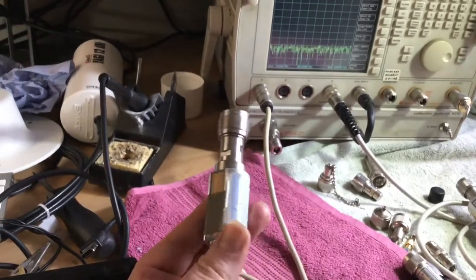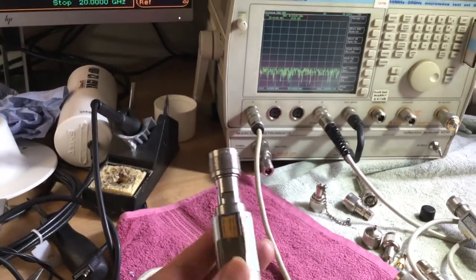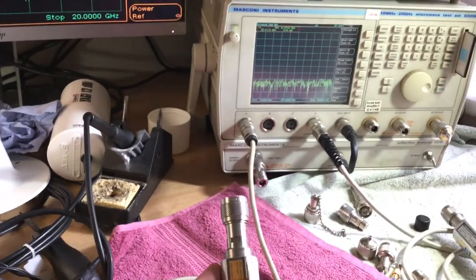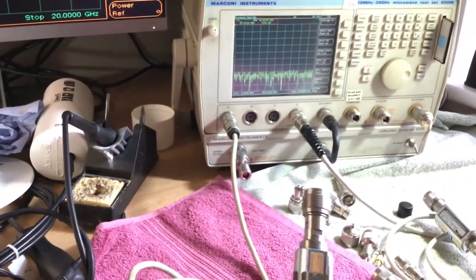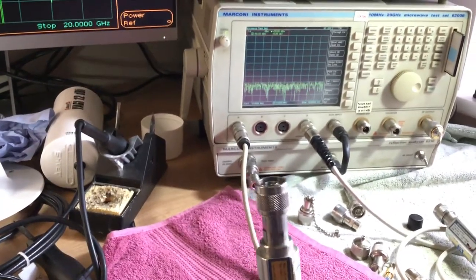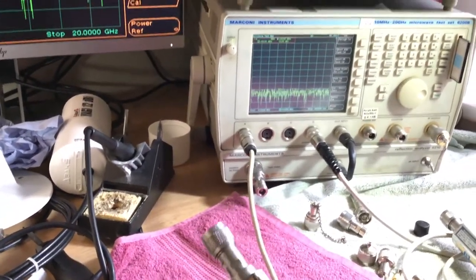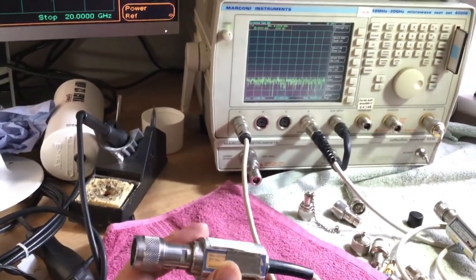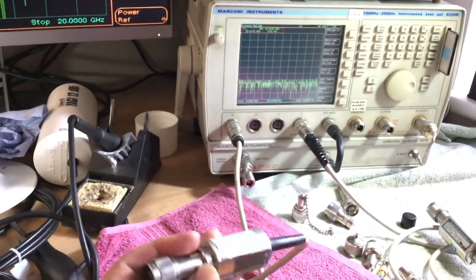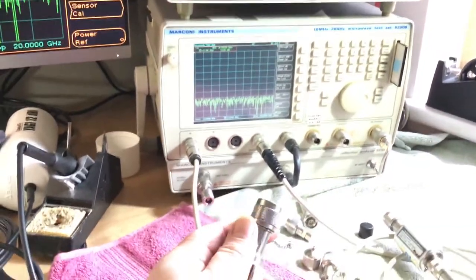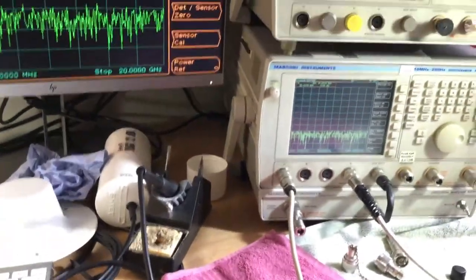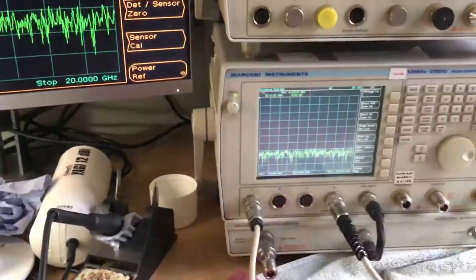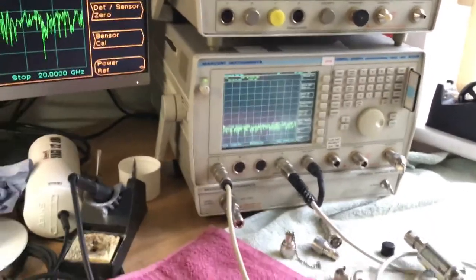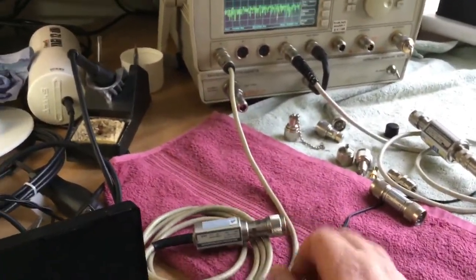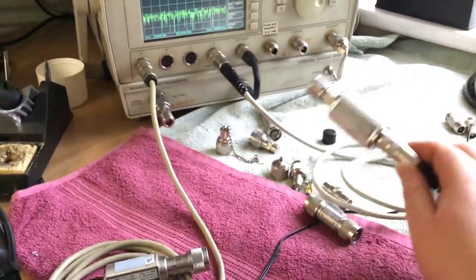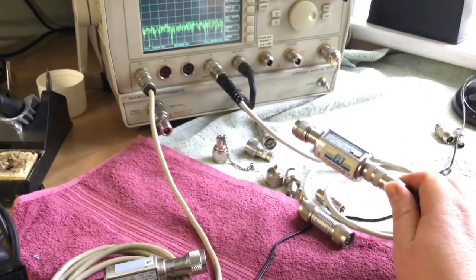This is a scalar detector, which is different to a power detector. This doesn't measure RF power in the same context as an RF power detector does. The scalar detector is a different sensitivity. It's very highly sensitive and it can't take much RF power at all. Indeed, it's only designed to work in the output level range of a test set. And so naturally, if the output level is too high, you can severely damage these sensors. Likewise with the power detectors, it doesn't take much power to make these fail.